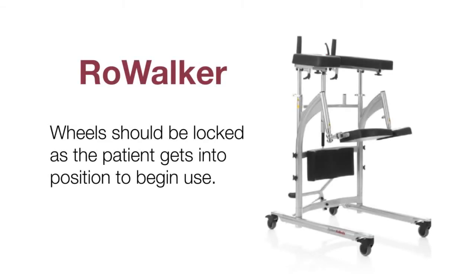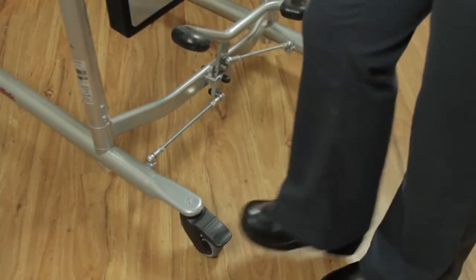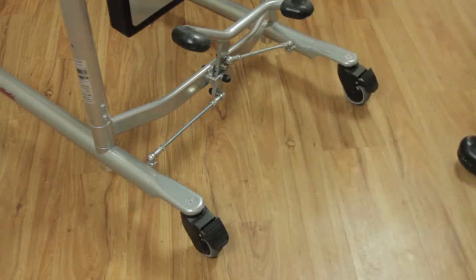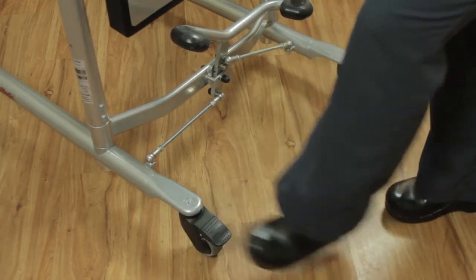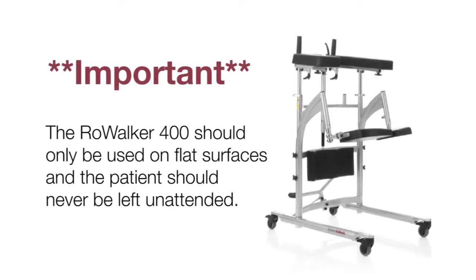Locking the wheels. The front wheels of the RoWalker 400 may be locked to inhibit movement. These should be locked as the patient is getting into position to begin use prior to walking. The directional locks on the back wheels may be locked for therapeutic purposes to direct intent of travel for the person using the device. To lock the wheels, step on the brake provided on each front and/or back wheel as desired. To release the wheels, apply pressure upward on the opposite direction until the lock clicks and the wheel movement is allowed. The RoWalker 400 should only be used on flat surfaces, and the patient should never be left unattended.